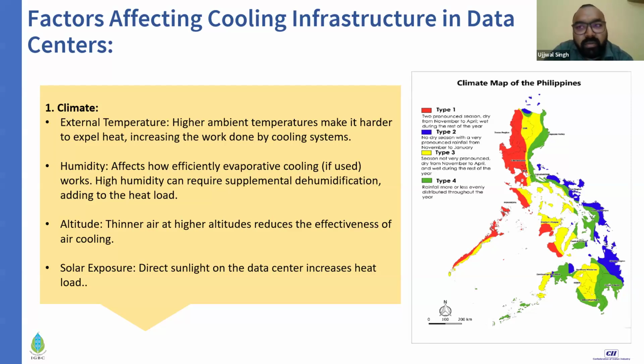If your external temperatures go way too high, you need chillers of higher rating, rated as per the climatic conditions or the highest temperature for your specific location. And with a long dry season, you'll have lots of sunlight adding to the heat gain for data centers, which should also be accounted for.